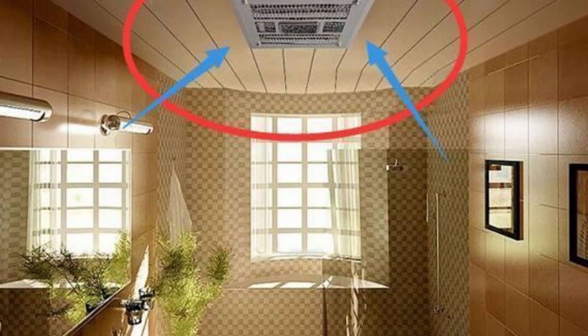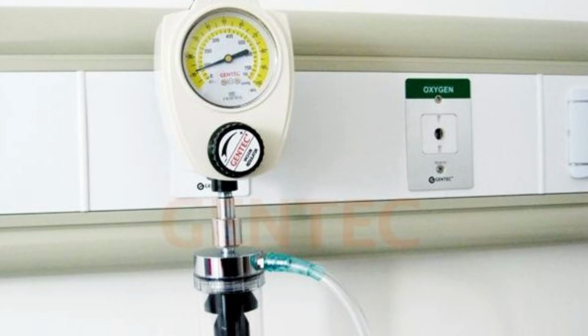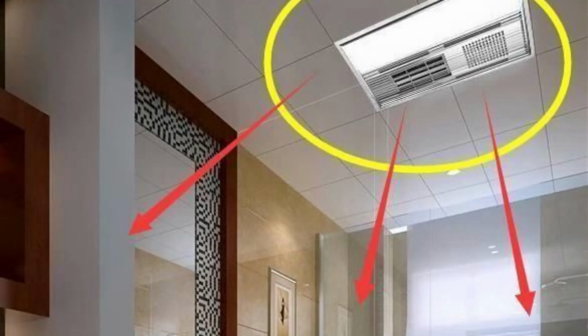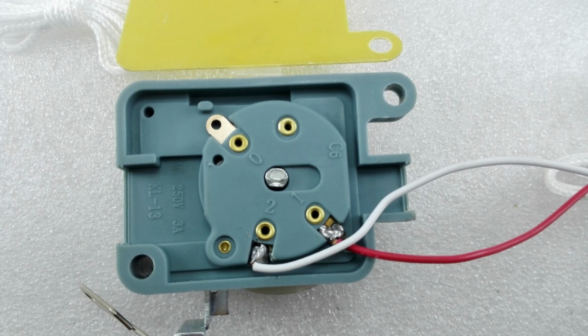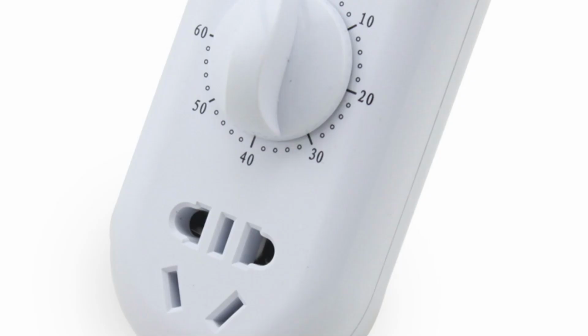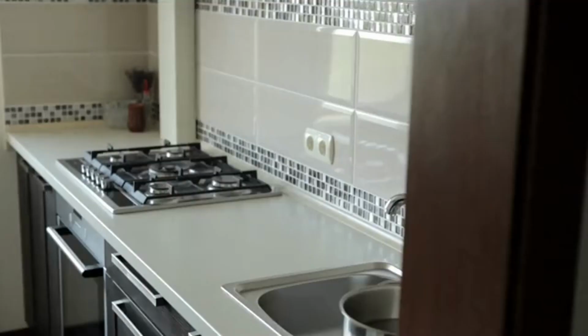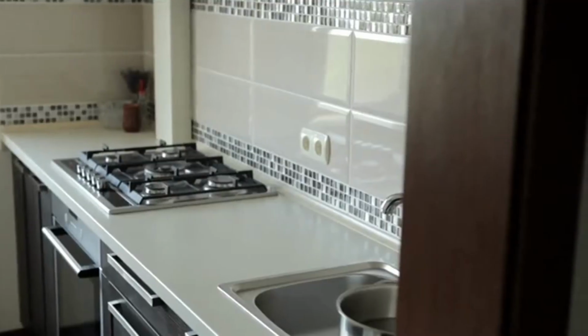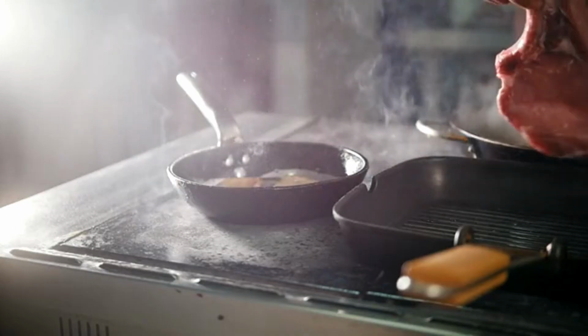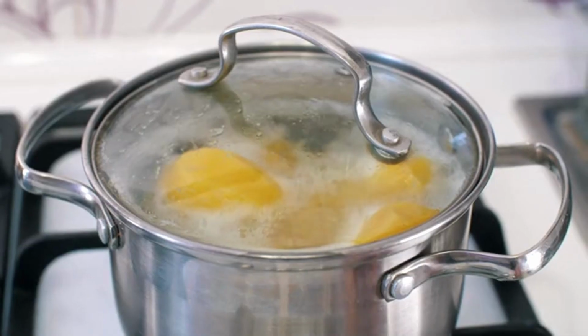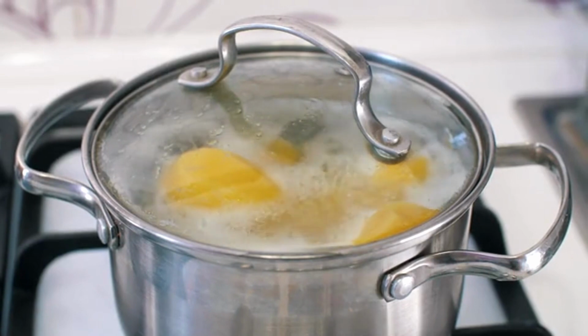determine proper vent placement. An intake in the bathroom rather than a simple exhaust fan, for example, will mean heated incoming air instead of just creating negative pressure and letting cold air find its own way in every time someone turns on the fan. You won't need to install a bathroom fan, of course, if you have an intake in there. Just be sure to put a timer switch so you and your guests can turn it on. Having an intake in or near the kitchen helps pick up general moisture and contaminants, but don't hook it up to your stove hood. It's not a good idea to send cooking grease through an expensive heat exchanger.